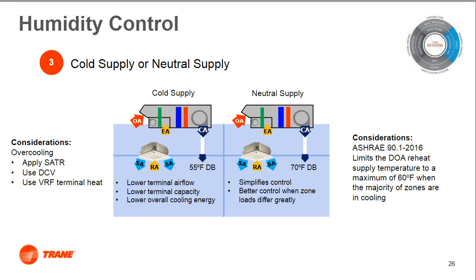There also needs to be some consideration when it comes to this method of outside air delivery. Overcooling can become an issue if not mitigated properly, and some steps may be needed to make sure that this does not happen. In order to avoid this, the following steps can be taken. Apply supply air temperature reset, use demand control ventilation, and apply heat to offset the overcooling in a space using the VRF terminal unit. Simply choosing a specific temperature, such as 55 degrees, seems to fit a rule of thumb, but it doesn't address the actual latent loads. To ensure space humidity control, an analysis to determine the appropriate supply air temperature would be needed. And that analysis would need to account for the design's space latent loads, as well as the design dehumidification weather.